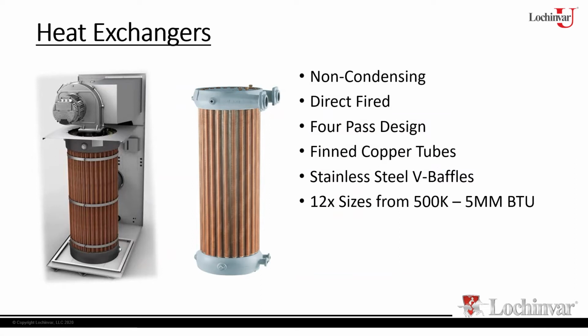You've got a bunch of copper tubes in this heat exchanger, and because of the number of tubes that we have, and because of the design of it being a 360-degree round heat exchanger that completely surrounds the burner, you have multiple passes. In this case, you have 4 passes. Your typical horizontal copper heat exchanger, like what you might see on a copper fin or a copper fin 2, is typically a 2-pass design. Here we get 2 extra passes because of the number of tubes, and because of that we get a little bit more contact time between the water and the flue gases, which helps improve our efficiency a little bit.